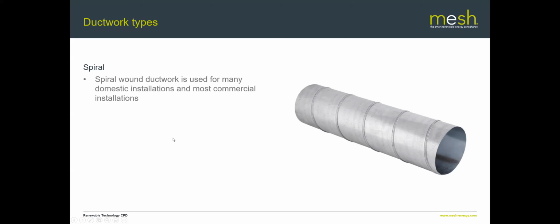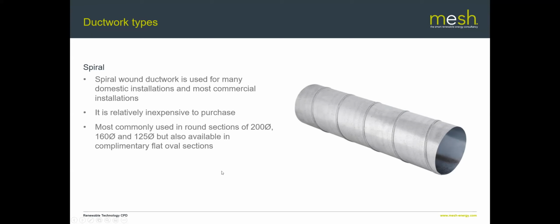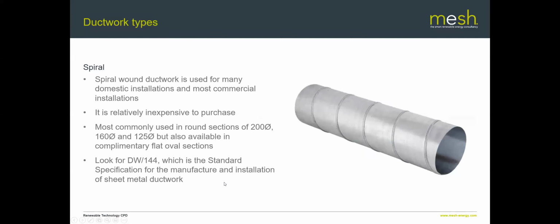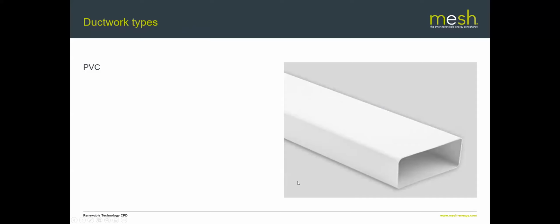And generally that would be what would be used for those sort of primary connections from the MVHR unit outwards. It's relatively inexpensive, as I said, and it's available in lots of diameters. There's flat oval versions of it as well, and it's all built to a standard, DW144. So that's the standard to look out for.